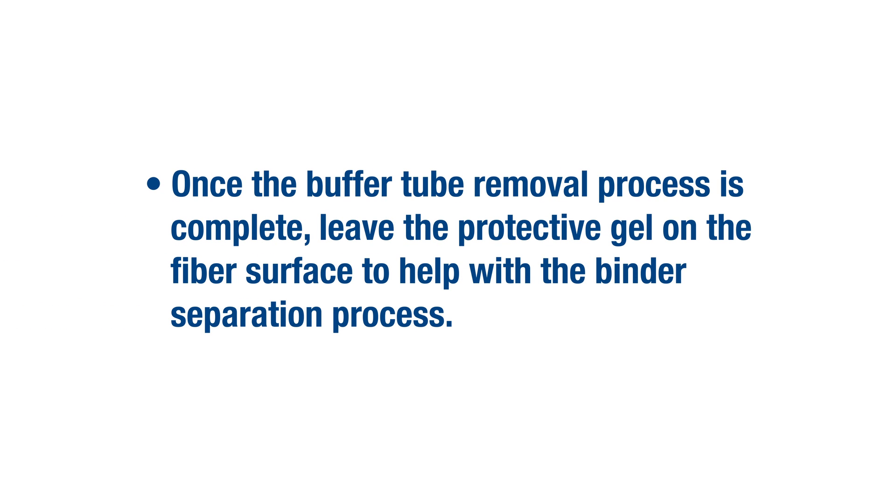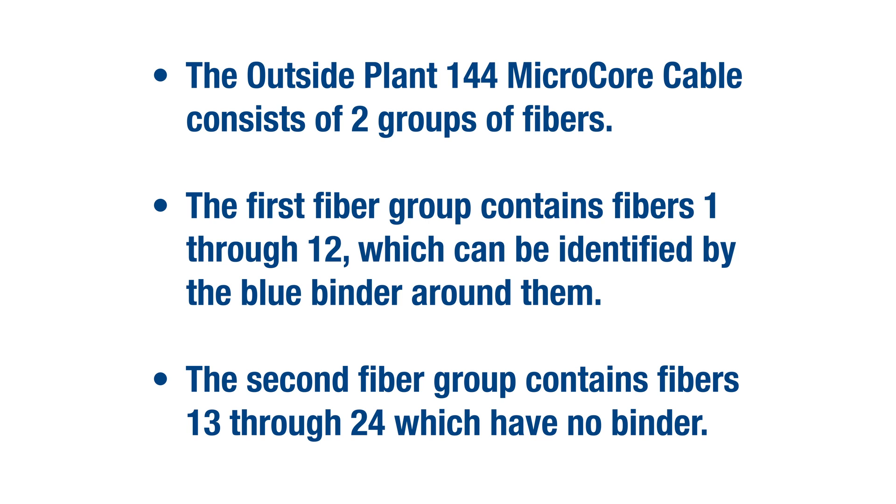Once the buffer tube removal process is complete, leave the protective gel on the fiber surface to help with the binder separation process. The outside plant 144 microcore cable consists of two groups of fibers. The first fiber group contains fibers 1 through 12, which can be identified by the blue binder around them. The second fiber group contains fibers 13 through 24, which have no binder.